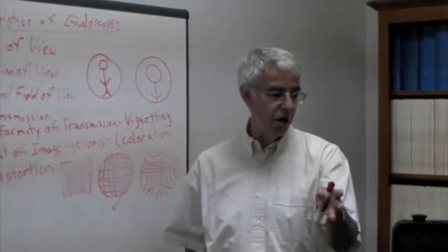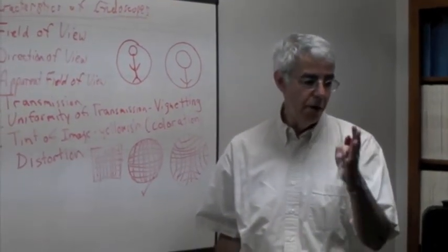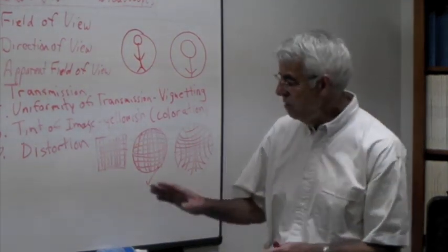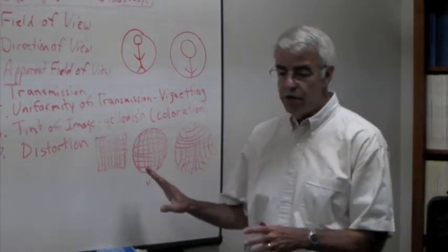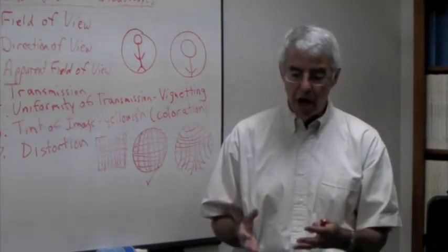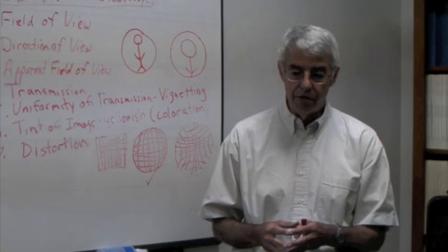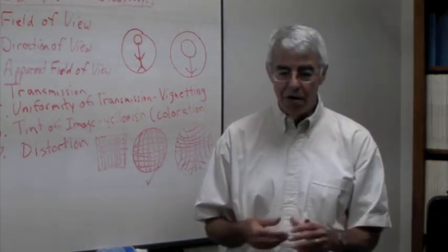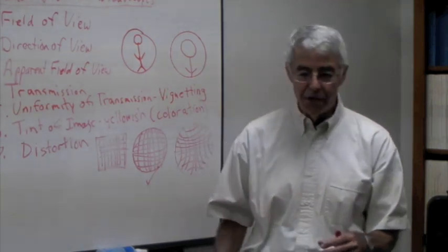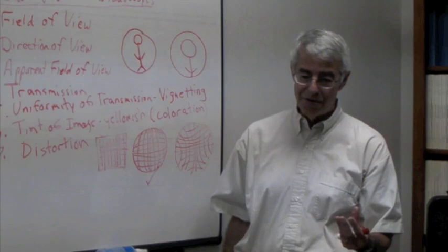However, an excessive amount beyond what they're used to for a particular kind of endoscope is not acceptable. You generally will not reject a scope for distortion because, as I said, the surgeons are generally tolerant of that characteristic.